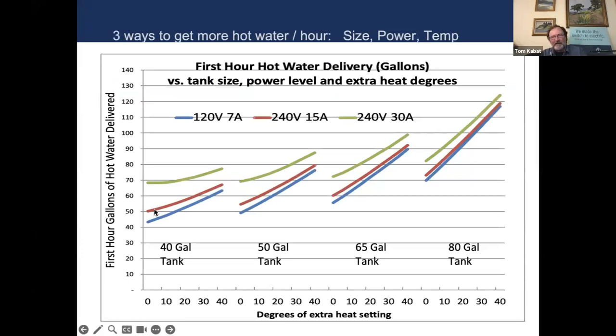This little graph is just showing heat pump water heaters. The vertical axis is how many gallons of hot water you can get in the first hour, morning rush hour. Here's a 70 gallon line going across, and these four groupings are a 40 gallon tank, a larger 50 gallon tank, or a 65 or 80 gallon tank. The numbers at the bottom are the number of degrees Fahrenheit of extra heat setting we'd put in if there was a mixing valve. At the bottom end of the scale is no mixing valve, and at the top end is a mixing valve with up to 40 degrees overheat—so that might mean setting it up to 150 Fahrenheit and then mixing cold water in with it, so you're still delivering 120 degrees into the pipe and nobody gets scalded.